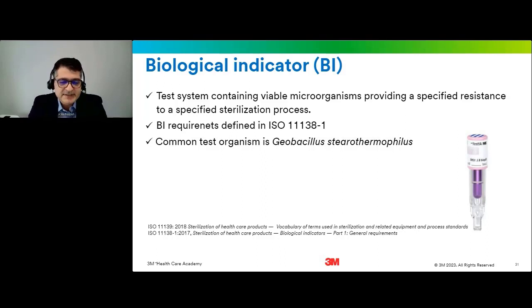Biological indicators. So we talked about physical monitors, we talked about chemical indicators, and now we are talking about biological indicators. The ISO 11139 definition for a biological indicator is a test system containing viable microorganisms providing a specified resistance to a specified sterilization process. As we discussed earlier, the general requirements come from ISO 11138, part one. The test organism is Geobacillus stearothermophilus, and the reason is that there is a lot of data in the literature showing that these spores are resistant to this modality. This is also an example of a biological indicator seen in this picture.